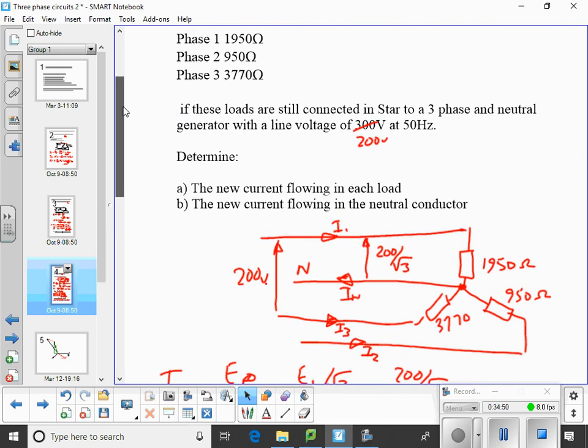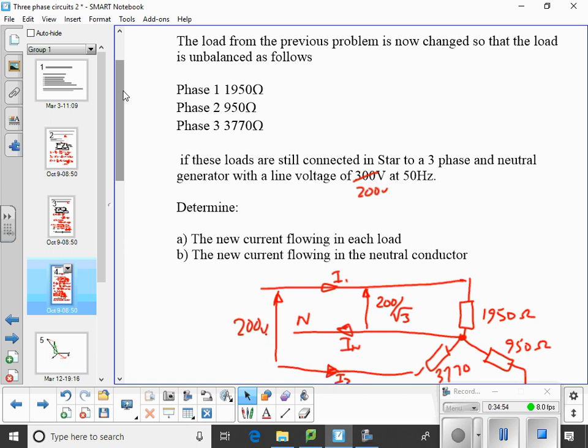So let's have a look, see what we get. So I want 1950 on the red phase. Well, we're going to do the balance first. Just check what you got, whether we got what you expected. Right. Red phase current and phase voltage, yellow current and line voltage, won't take any note of the watts, okay? And this one down here, doing the blue phase current, and that one is the neutral current. At the moment, we've got 1950 on all three.